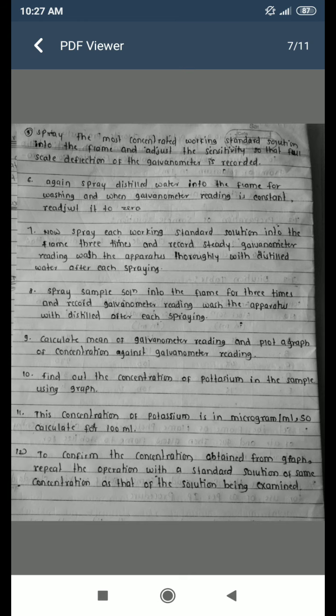The concentration of potassium is in micrograms per ml. To confirm the concentration obtained from the graph, repeat the operation with a standard solution of the same concentration as the solution being examined. The observation table includes: solution, concentration in micrograms, galvanometer readings for the first, second, and third sprays, and the mean galvanometer reading for solutions A, B, C, D, E, and the sample.